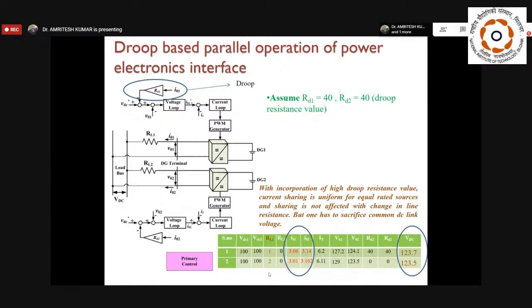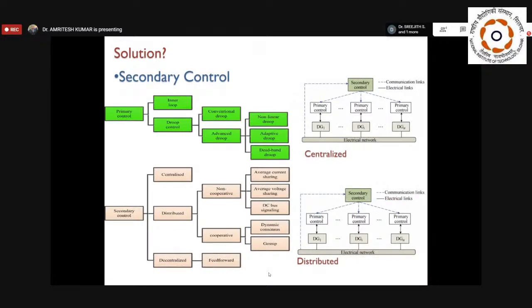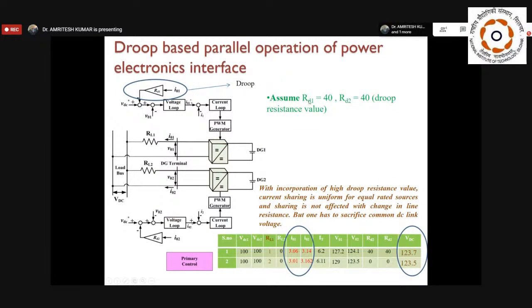So what can we do? I think this primary control is not enough for maintaining both uniform current and the DC link voltage at the reference value that we desired, around 250 volt. So the solution is obviously to go for the other control, that is the secondary control. The first one is the primary control. Here I assumed that I have increased the value to 40 to get uniform current sharing, but the problem is that we arrive at a very low DC link voltage. But you can't just directly fix the value to 40 or 30 or whatever.